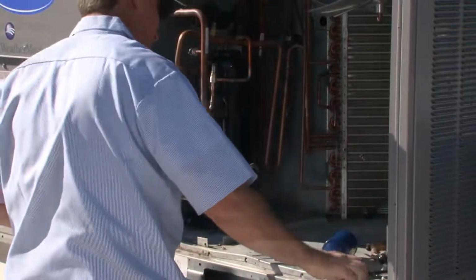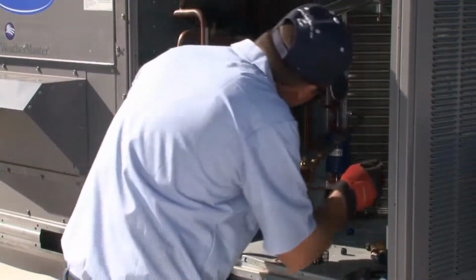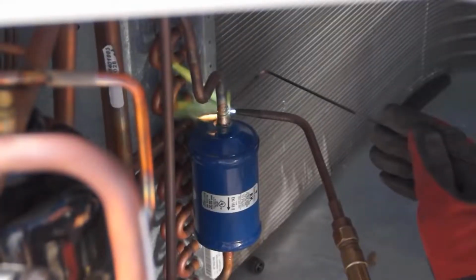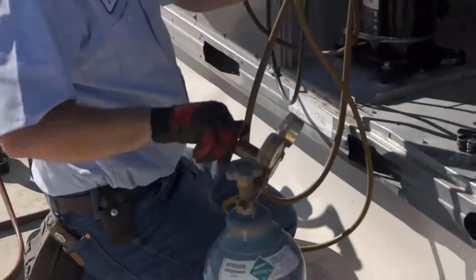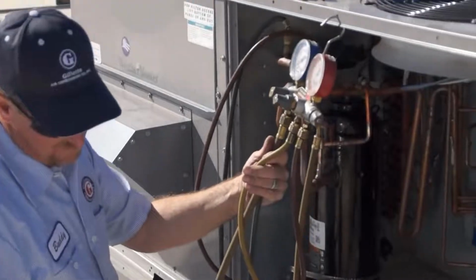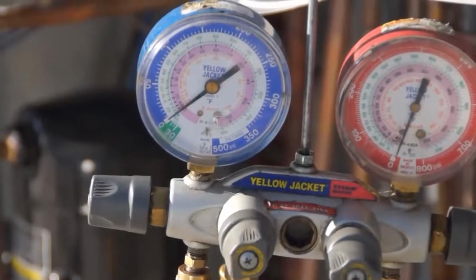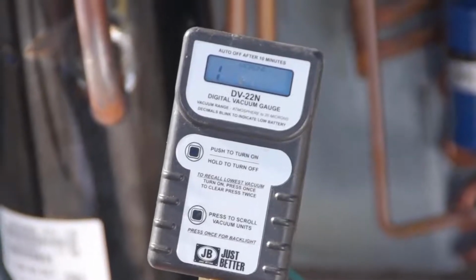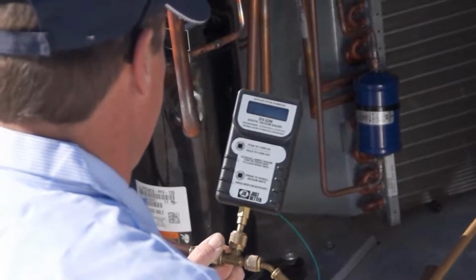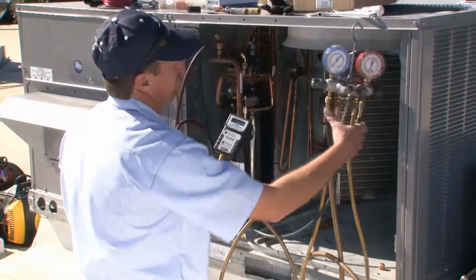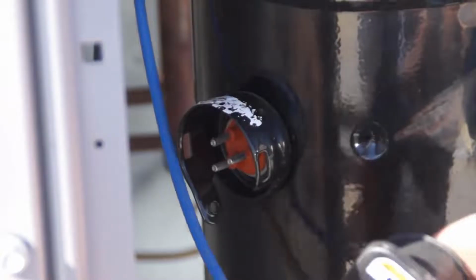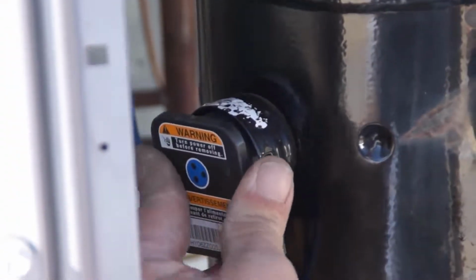Next, install a new filter dryer to remove any contaminant introduced while the system was open. Once the system is sealed again, begin leak test procedures by adding nitrogen, monitoring gauges, and identifying and fixing leaks as needed. Next, begin the evacuation procedure to prepare the system for new refrigerant. While waiting, reconnect all electrical points and switches.